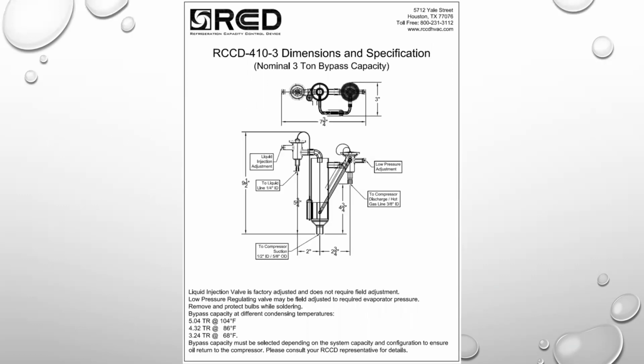This is the 410-3. Just to point out some things, in the lower left-hand corner, you'll see bypass capacity at different condensing temperatures. What you will notice is that at 68 degrees, this thing will bypass 3.24 tons. Now, 68 degrees would actually be about a 50 to 55 degree outdoor air temperature. And 104 will probably be about an 84 to 90 degree outdoor air temperature. This is the condensing temperature inside the condenser.